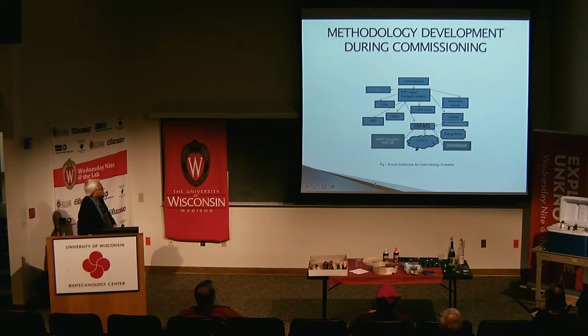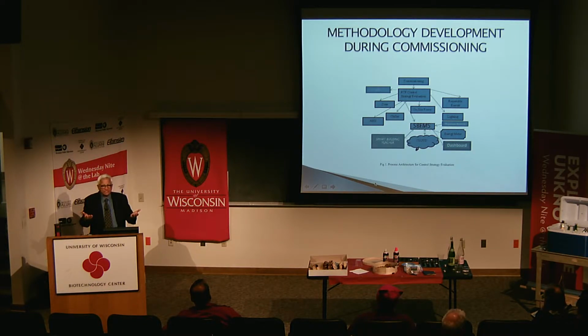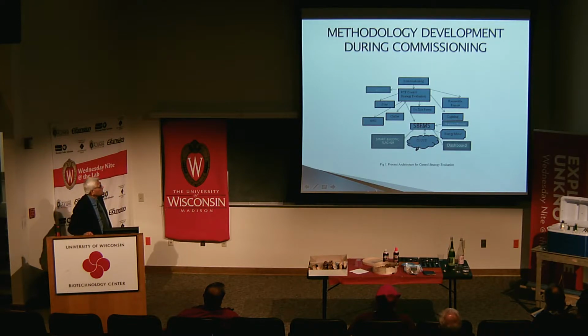Now here is my methodology, how to come up with control strategies corresponding to outdoor air temperature. So what I have suggested is, during the commissioning process, when the building is built, it goes through several stages. If you look at one stage almost in the end, it's called operational phase with occupancy. So in other words, you are testing the control strategies and all that before the entire commissioning process is complete. So this is what is done. This is the commissioning process.